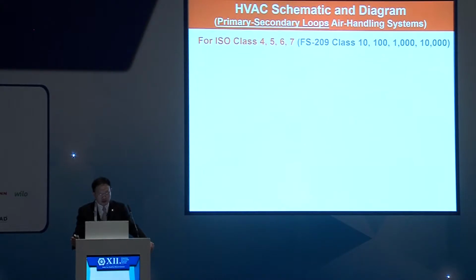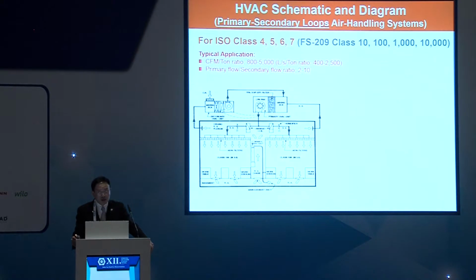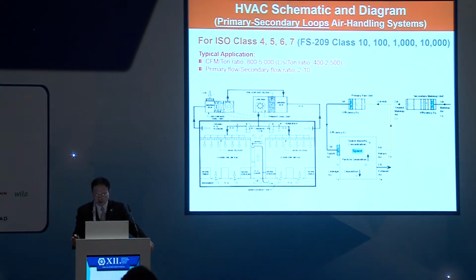For middle-class clean rooms, ISO 4, 5, 6, 7, your airflow versus cooling load range is much higher. Could be 400 up to 2,500. In this case, you may want to use primary and secondary air loops. So in this case, you have a designated outside air unit. You have a return air, merged with the treated outside air, and so you use two units.